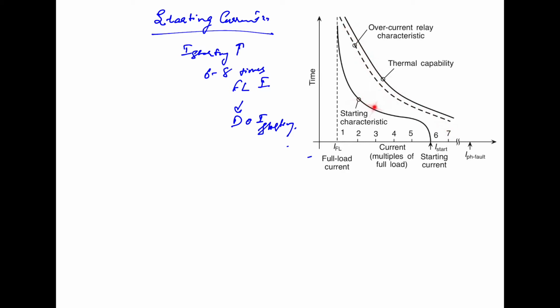So it must be above the starting characteristics but below the thermal characteristics of the motor. This will ensure that the protective relay does not operate during the starting of the motor, but it will positively operate when the load exceeds the motor thermal capability. The starting current is taken care of by the starting current characteristics, and we will have this overcurrent relay characteristics and the thermal capability characteristics. Now you will see that the overcurrent characteristics is between the starting characteristics and the thermal capability characteristics.